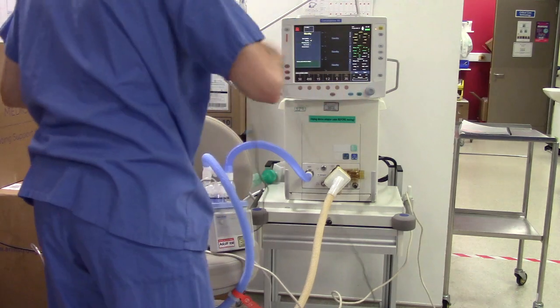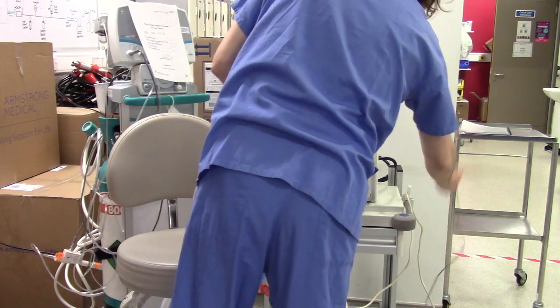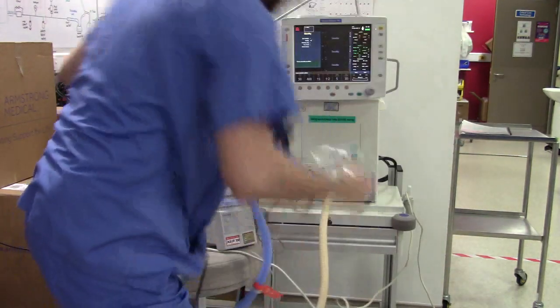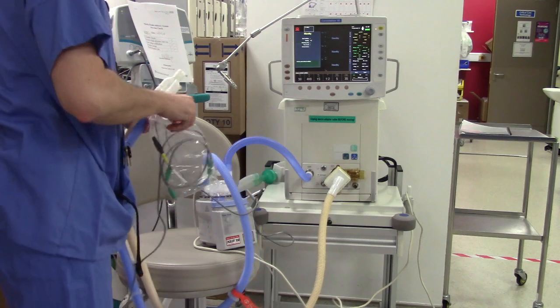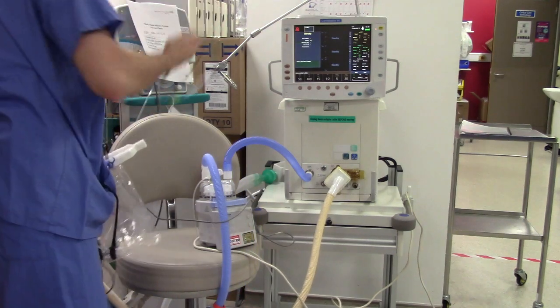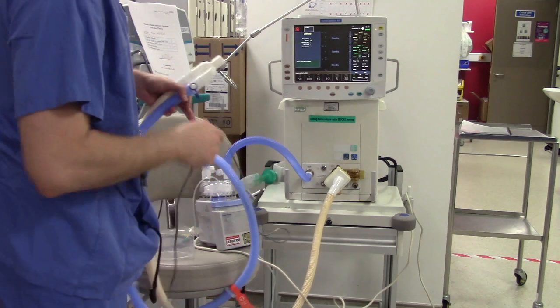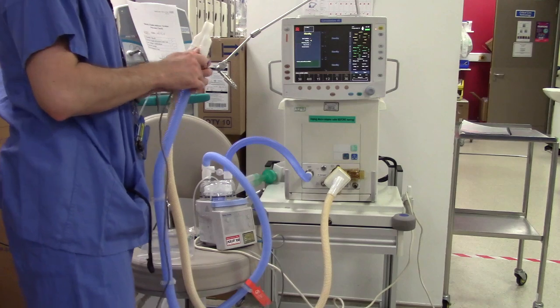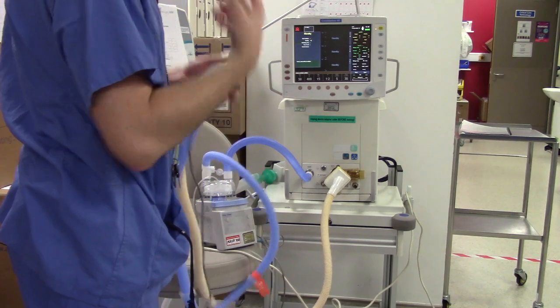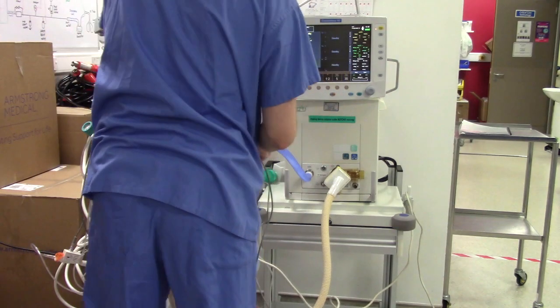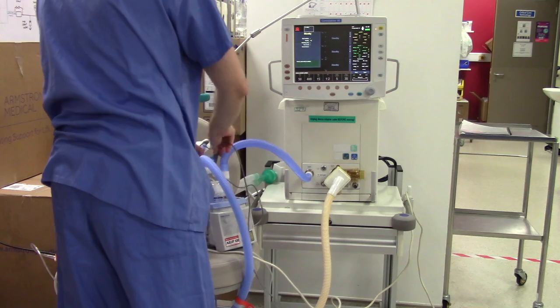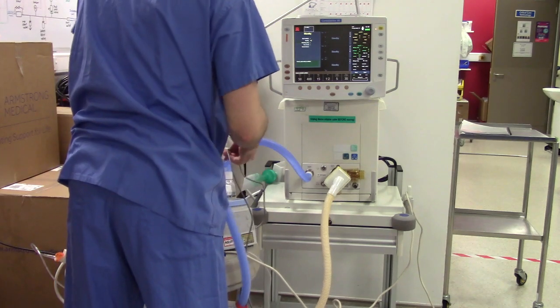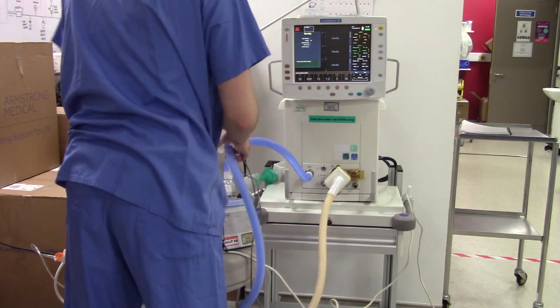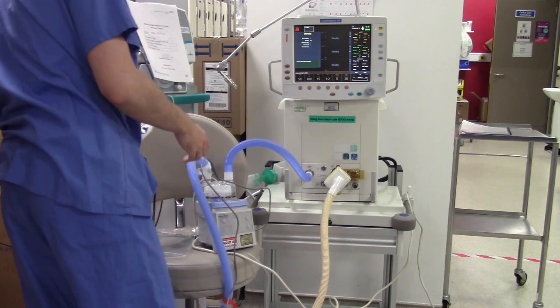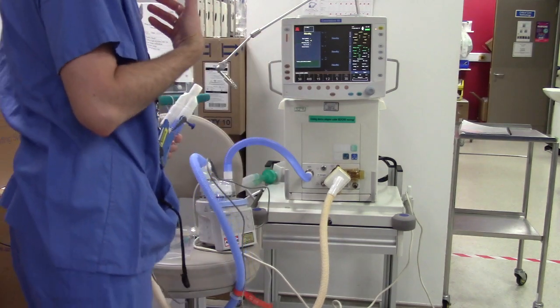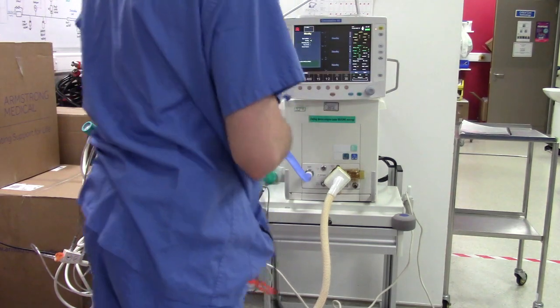And we need to connect special wires as well. There are two sets of wires. This wire is called the temperature sensor, and this is a heating wire. I'm not talking about them yet. What this wire does is detect the temperature at this point, just before going to the patient, and at this point. This way it can detect if it's overheating or if it's heating enough the air, yeah, or the water that's humidifying the air.